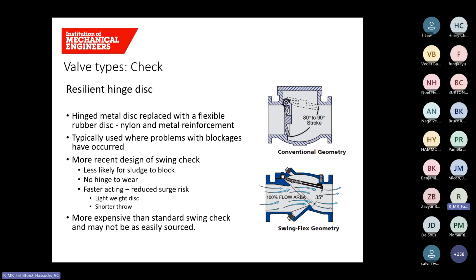The next check valve is the resilient hinge disc. In this valve, the metal disc is replaced by a flexible rubber disc, and it tends to be used with sludge where you might have blockages occurring. It's better for this application because the disc doesn't have to move as far, and it is also quick to open and close, meaning you don't get the same risk of surge that you do with a conventional swing disc valve. They are more expensive to buy, and they are less available just because they're a newer design and less commonly used.